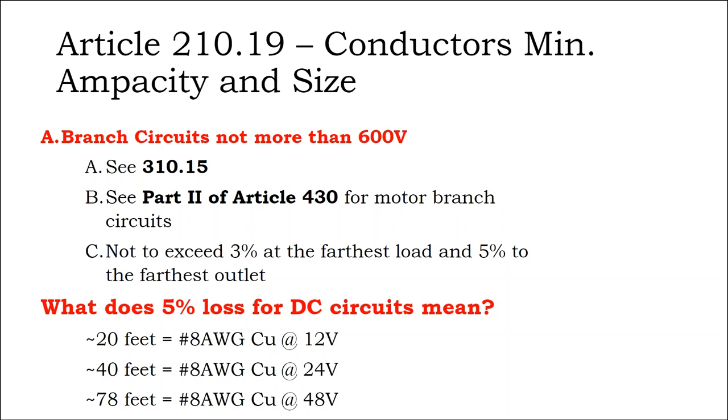Most solar arrays are designed for a 2% voltage drop, because after all, solar is supposed to generate electricity, and generally speaking, it is going to be cost effective to keep upsizing your wire to reduce resistance. But there is a point where upsizing your wire even further gets into diminishing returns. So when solar is designed around a 1.5 to 2% voltage drop, they're thinking about economics, not what is the bare minimum level of acceptability for voltage drop, which is defined as you don't want more than a 3% voltage drop from that breaker to the load, with a little bit more of an exception given for branch circuits that have multiple outlets that could have up to a 5% maximum voltage drop.